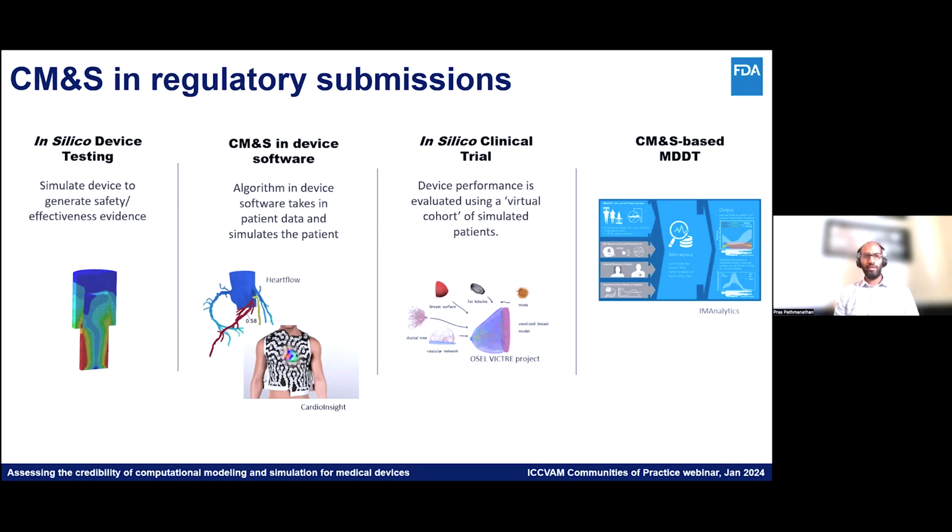And yeah, in silico testing, a computational model is developed of the device. Some kind of virtual testing is done, and those virtual test results are submitted to CDRH, usually together with other bench, animal, or clinical data.